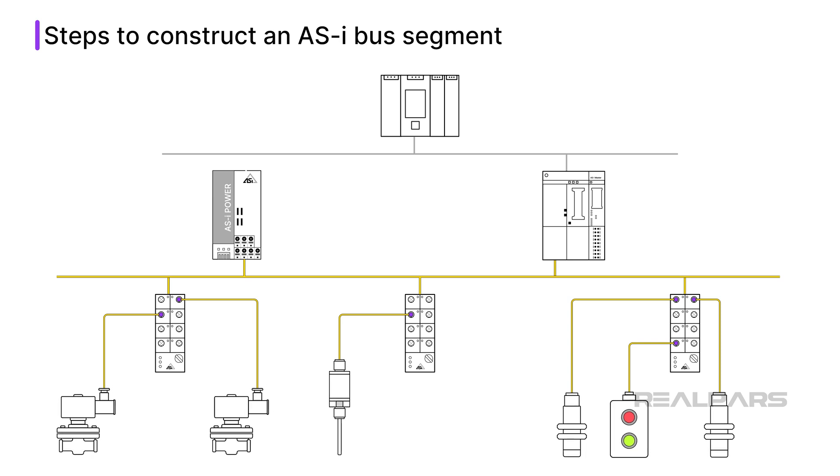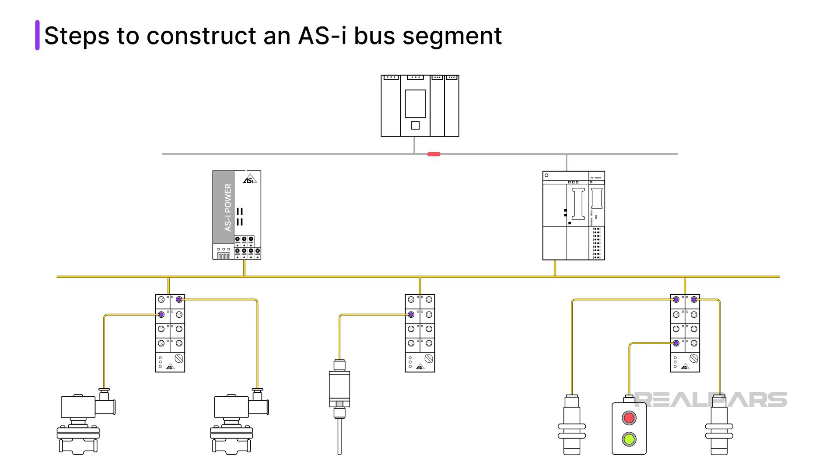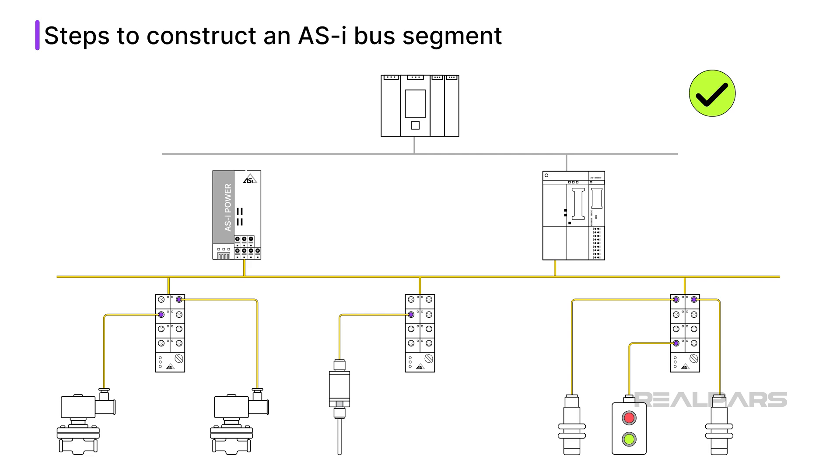Finally, I test the devices by reading statuses and sending commands, depending on the capabilities of each device. I send open commands to the valves and verify that I receive position feedback. I press each button on the push-button stations and trip the proximity sensors to verify proper detection. I check the temperature sensor to see if it is reading the correct temperature for where it is placed. All good! My AS-i bus segment is installed and working.